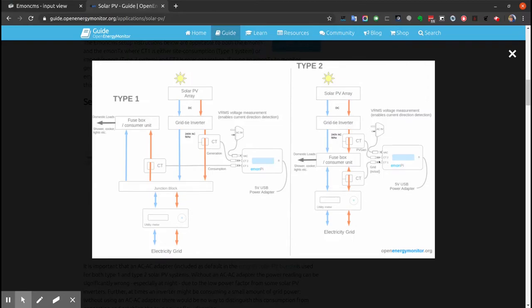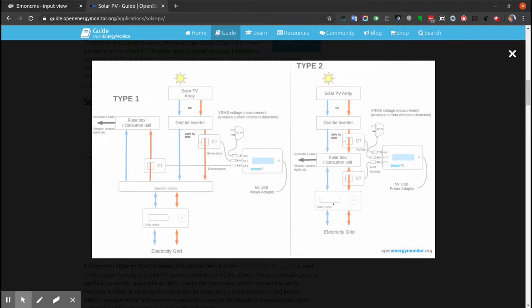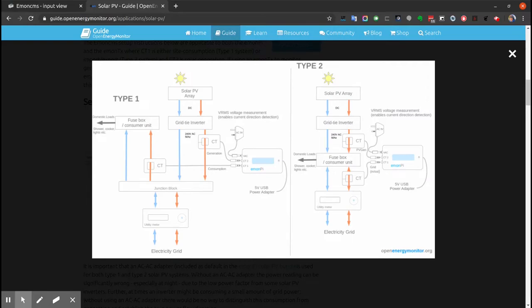Looking at this diagram, we should connect CT1 to monitor the grid import/export. That's one of the cables going into or out of the utility meter. CT2 should be clipped around the output from the Solar PV array, the AC output. CT2 should always be clipped around the live or neutral cable and not both.